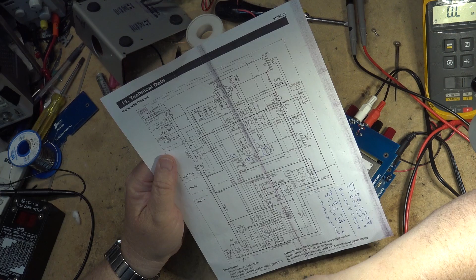Let's look at pin number 3 for the vacuum tube and watch the voltage here. We got 12 volts on it when it first starts. That's fine, because 12 volts is fed in through the transformer, and then the boost comes on and should boost it up to about 220 volts. There we go, 230, 240, that's good.